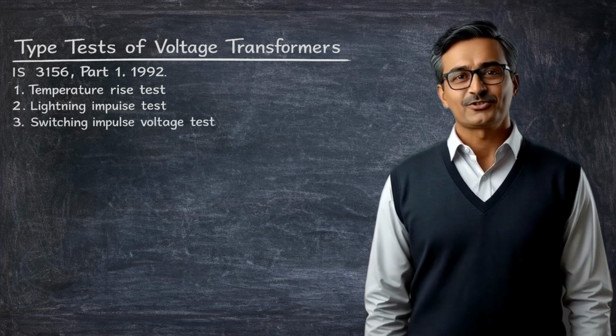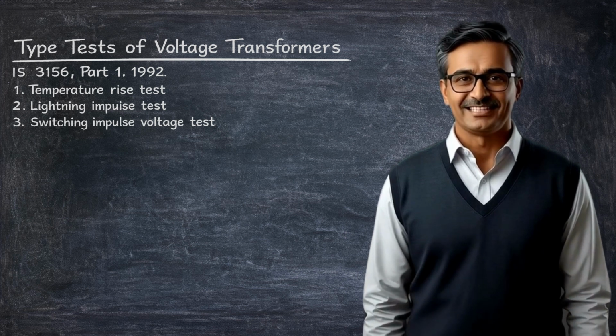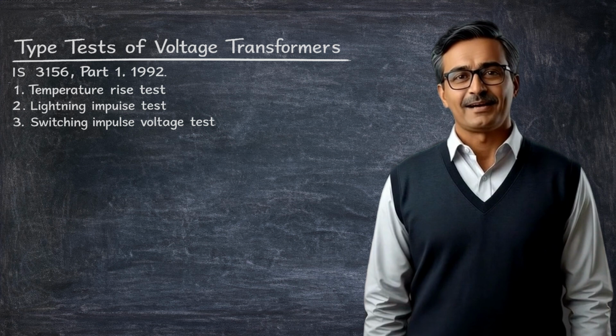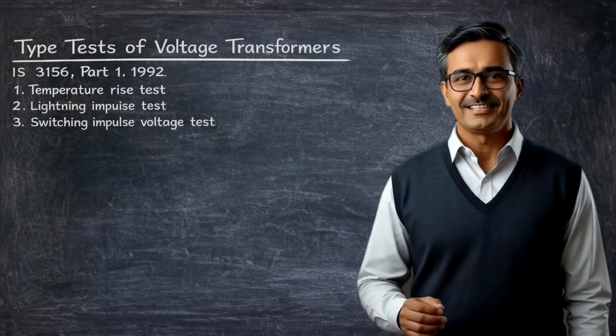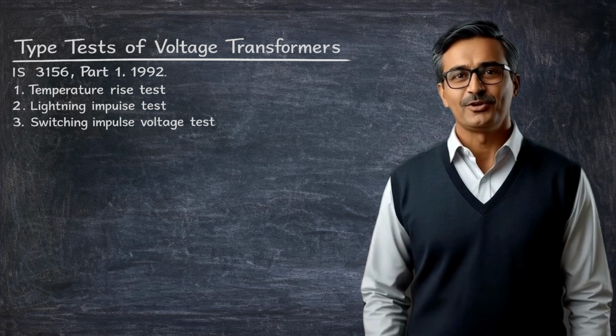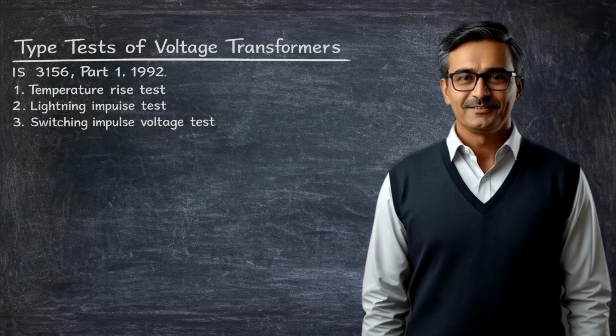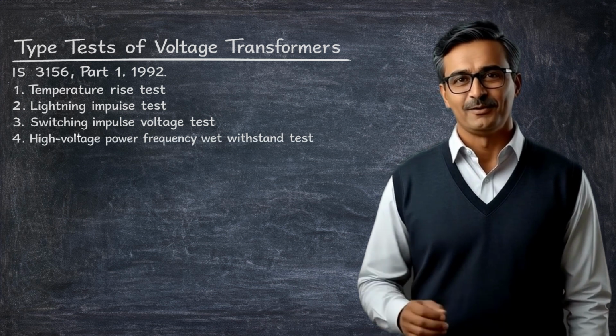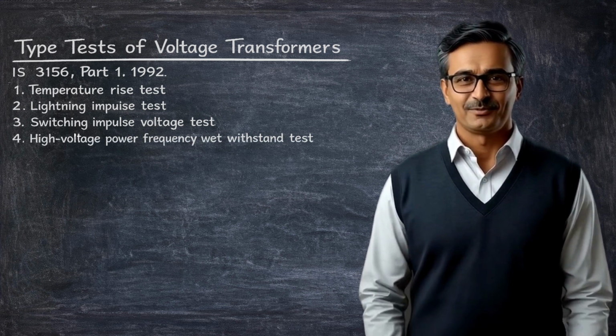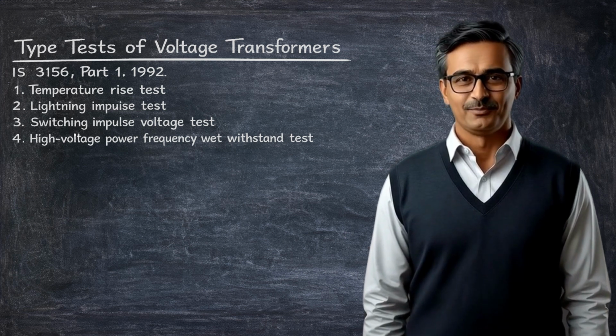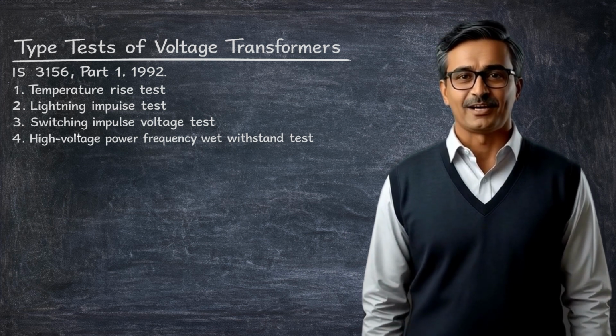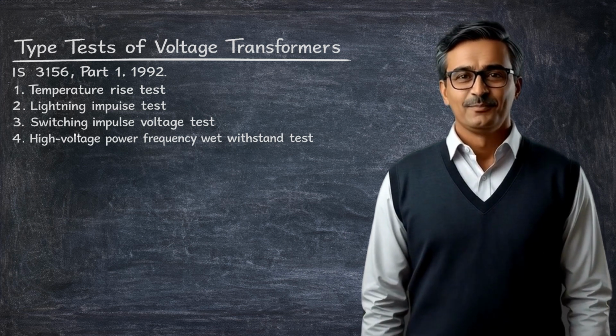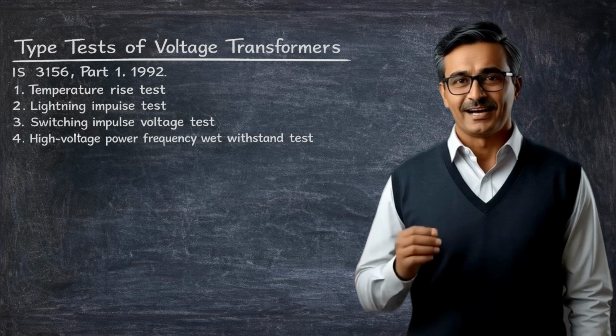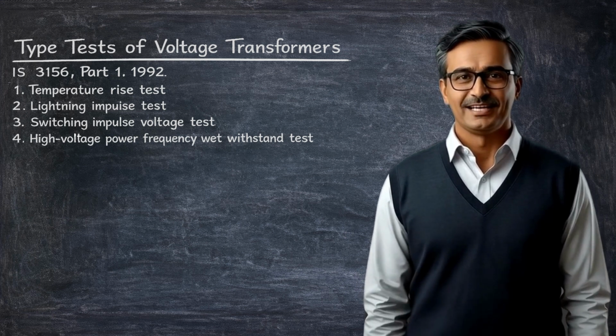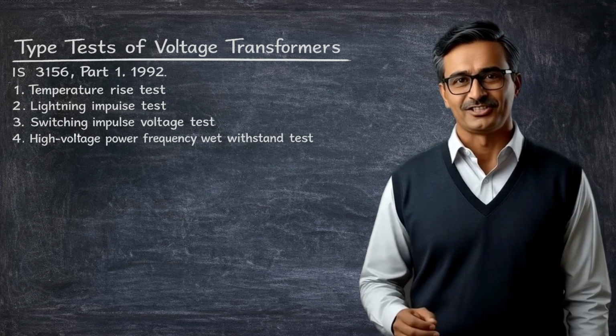The third test is the switching impulse voltage test. This test is required for voltage transformers rated at 420 kV and above. It simulates the overvoltages produced during switching operations in high voltage power systems. Next is the high voltage power frequency wet withstand test. This test is performed on outdoor voltage transformers up to and including 245 kV. During this test, the transformer is subjected to high voltage under wet conditions, usually by spraying water on the insulation surfaces. This helps verify the insulation performance under rain or moisture conditions.